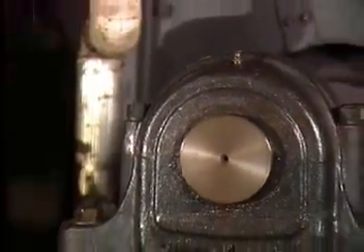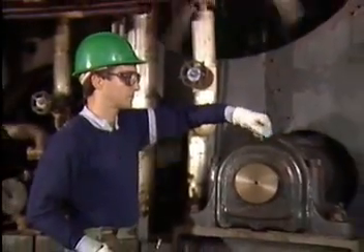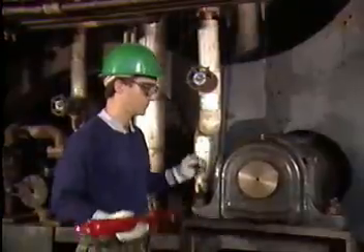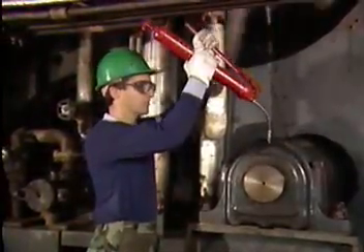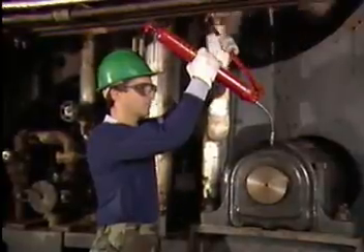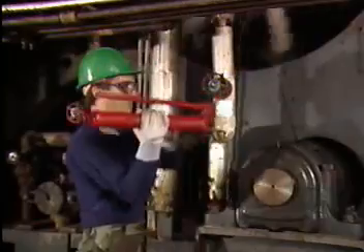shaft seals. In this case, it is very important to add grease slowly to the housing so that the shaft seals are not damaged. A good rule of thumb is to pump the grease gun no more than 2 or 3 times unless specific plant guidelines state otherwise.